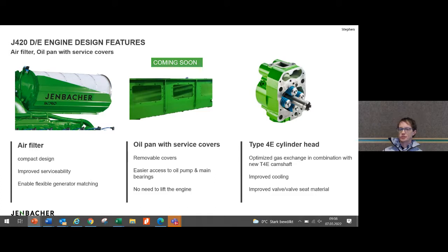As Martin mentioned, the air filter is new. So with the increased height of the turbocharger, the air system becomes the most obvious visual change for the genset. It's a new compact design. The serviceability has been improved. Because of its compact design, it gives us more flexibility with generators.